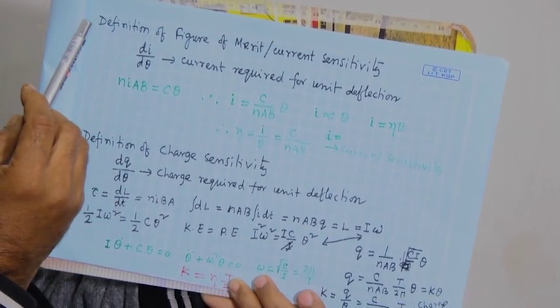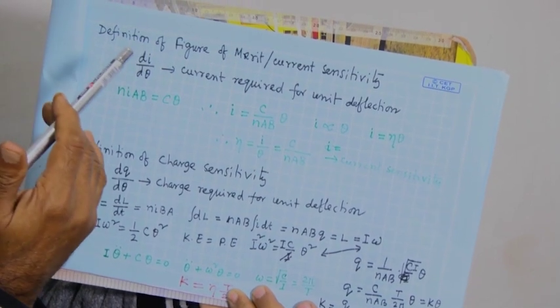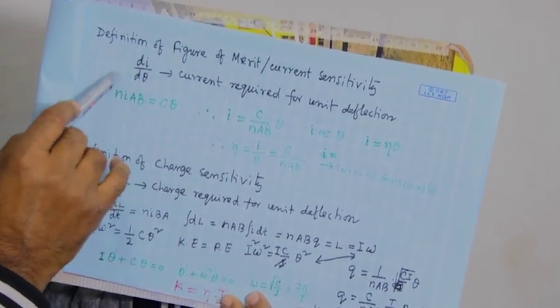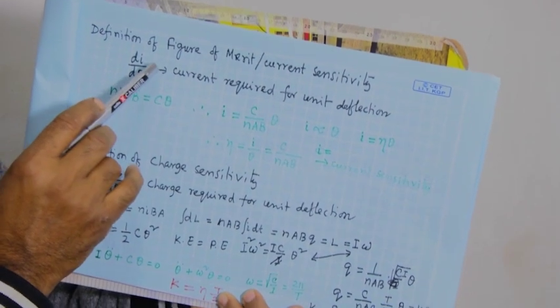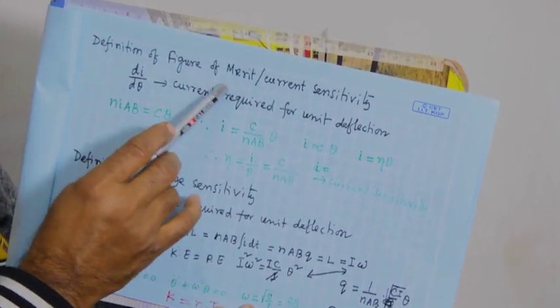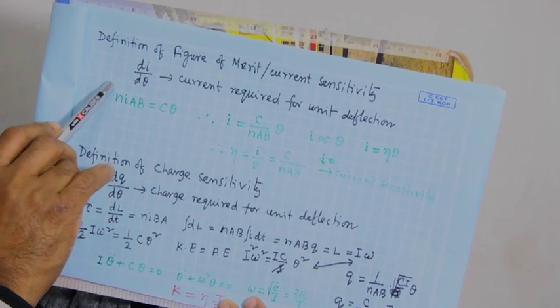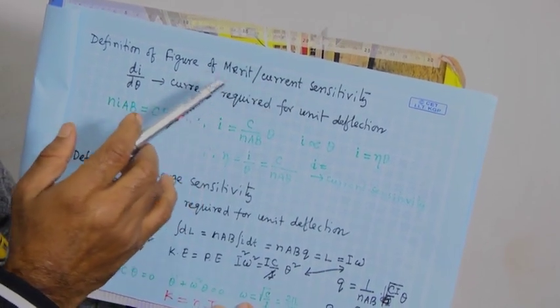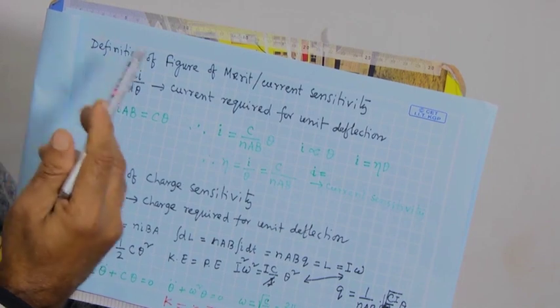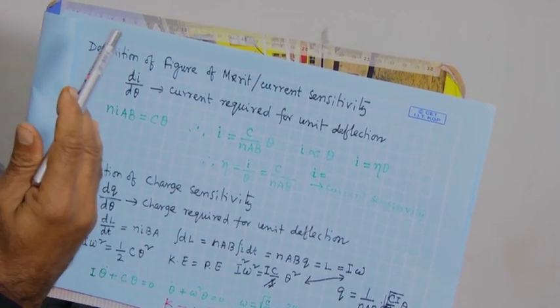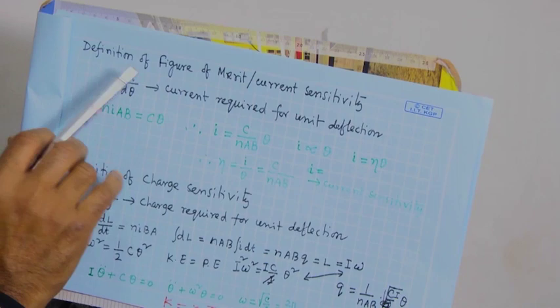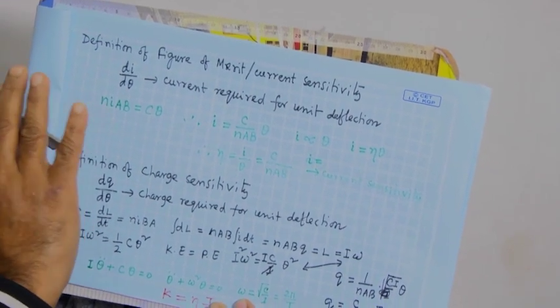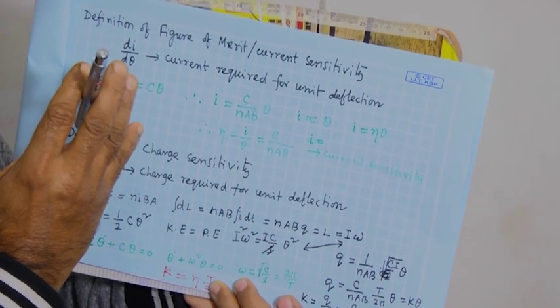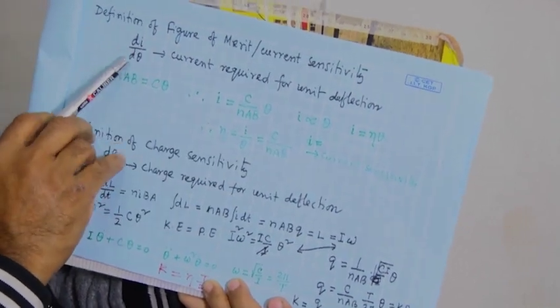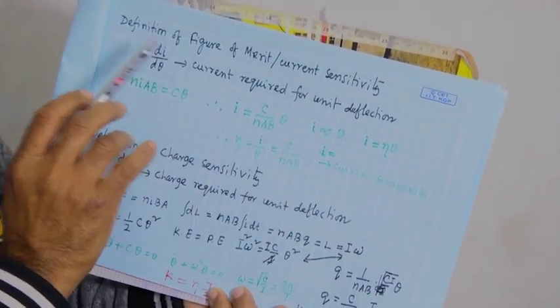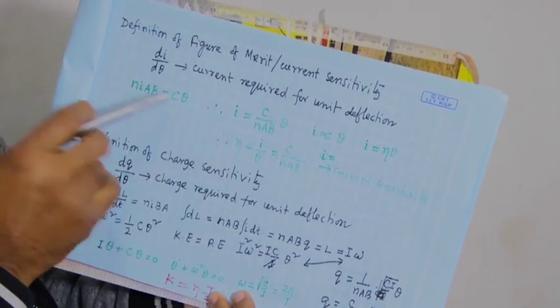If a small current is required, then this value will be smaller. So a smaller value of figure of merit is better, meaning it is very current sensitive. We need a very small current to rotate by a unit angle.